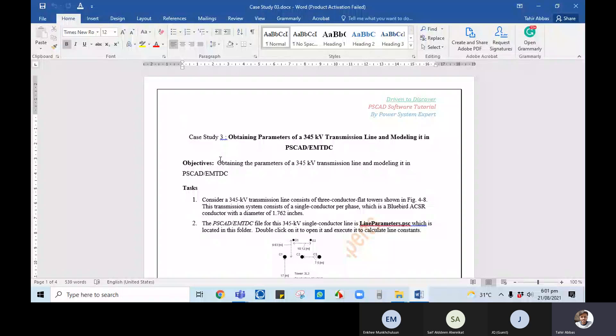At the planning stage, if a new plant is interconnected in the system, we need to measure the parameters of the new line. For that purpose, we use tower and conductor information. With the conductor radius, ground-to-conductor data, and other required data, we can calculate R, X, and B — called line constants. By using these line constants, we can get R, X, and B values and put them into the pi model for analysis like load flow.